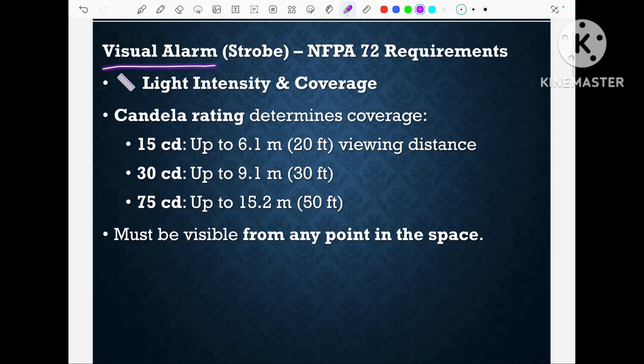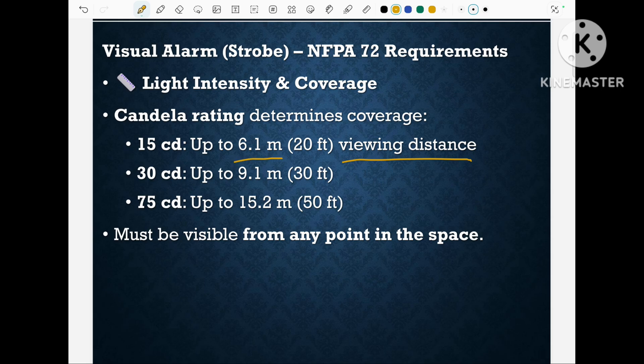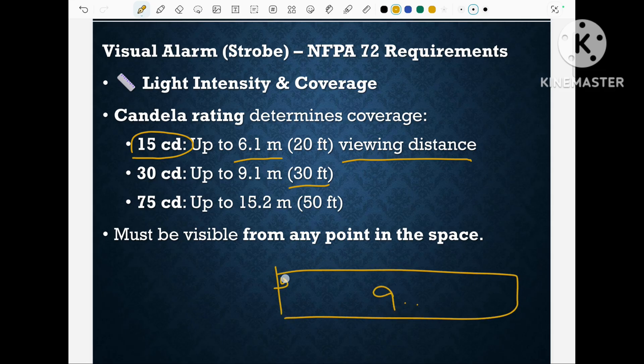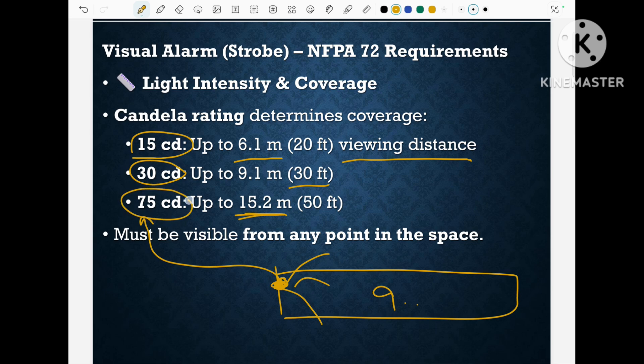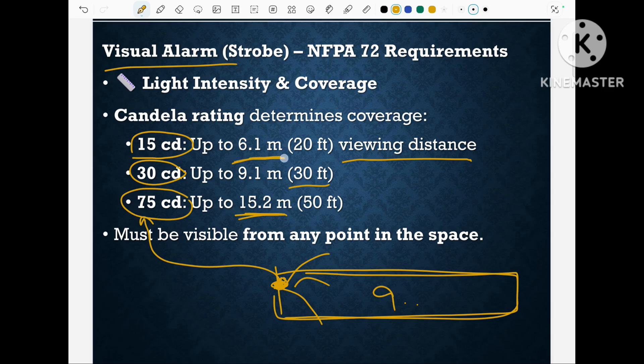The visual alarm must be selected based on the viewing distance. If the viewing distance is up to 6.1 meter, we can go for a visual alarm which produces 15 candela. If the corridor length or viewing distance is 9.1 meter, the visual alarm should produce 30 candela. If the viewing distance is 15.2 meter, we have to select a visual alarm that can flash up to 75 candela. So based on the viewing distance, we select the visual alarm — lower candela for shorter distance and higher candela for longer distance.